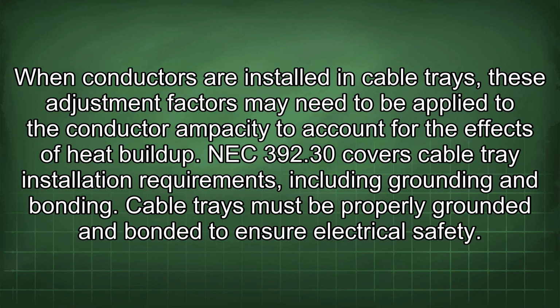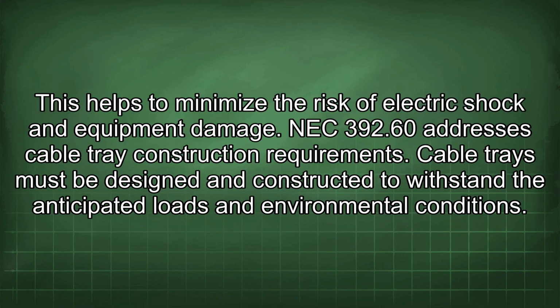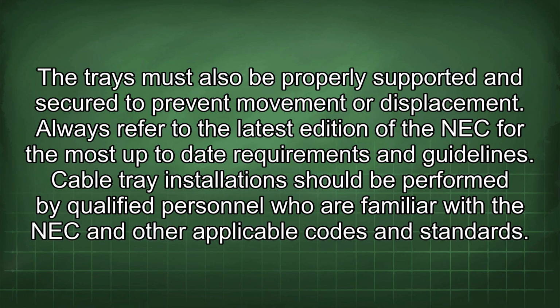these adjustment factors may need to be applied to the conductor ampacity to account for the effects of heat buildup. NEC 392.30 covers cable tray installation requirements, including grounding and bonding. Cable trays must be properly grounded and bonded to ensure electrical safety. This helps to minimize the risk of electric shock and equipment damage. NEC 392.60 addresses cable tray construction requirements. Cable trays must be designed and constructed to withstand the anticipated loads and environmental conditions. The trays must also be properly supported and secured to prevent movement or displacement. Always refer to the latest edition of the NEC for the most up-to-date requirements and guidelines.